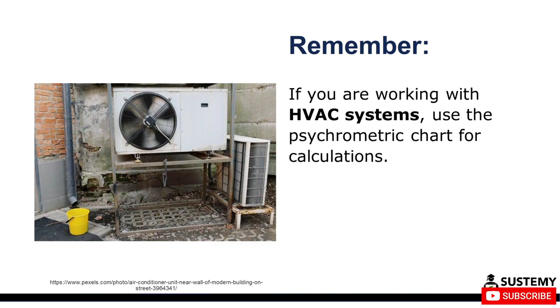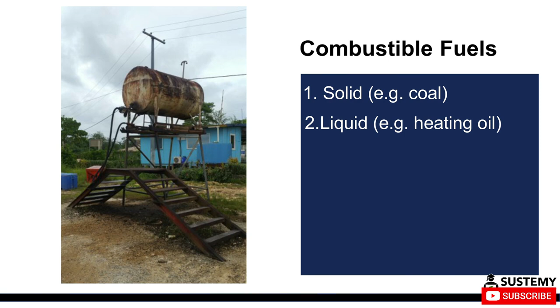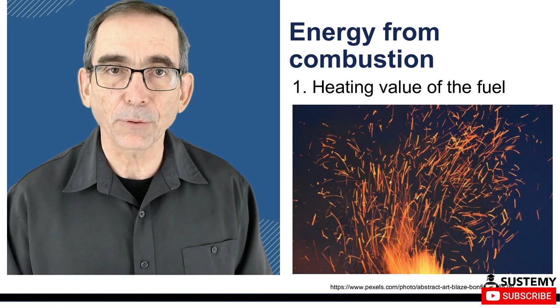Characteristics of fuels and combustion. Many facilities directly combust fuels, which may be solid, such as coal, liquid, such as heating oil, or in a gaseous form, such as natural gas. To understand the amount of heat generated during combustion, you need to know the heating value of the fuel and its mass flow rate. And you usually assume that perfect combustion occurs with no excess air. So the heating power provided equals the fuel mass flow rate times the heating value.